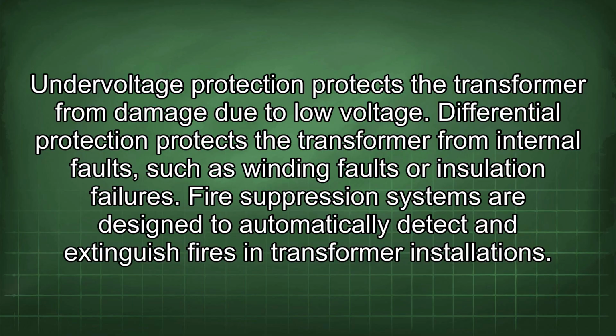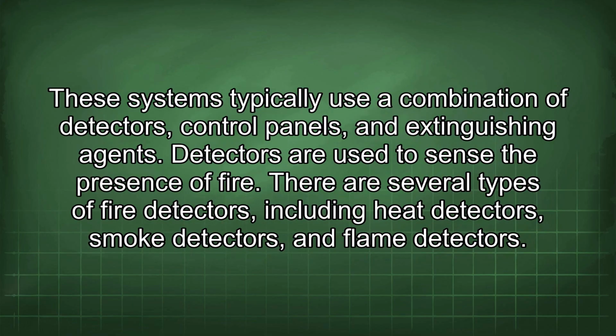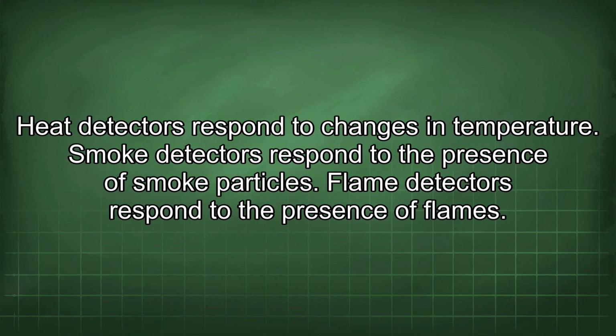Fire suppression systems are designed to automatically detect and extinguish fires in transformer installations. These systems typically use a combination of detectors, control panels, and extinguishing agents. Detectors are used to sense the presence of fire. There are several types of fire detectors, including heat detectors, smoke detectors, and flame detectors. Heat detectors respond to changes in temperature. Smoke detectors respond to the presence of smoke particles. Flame detectors respond to the presence of flames.